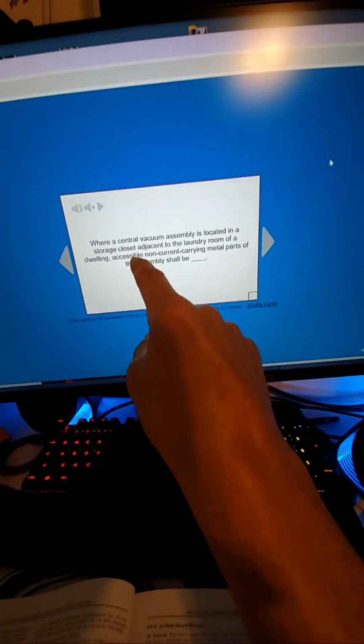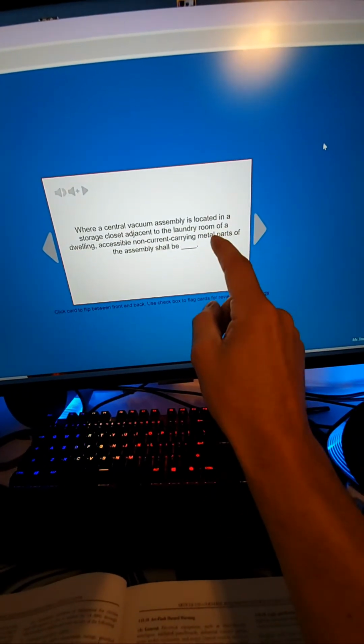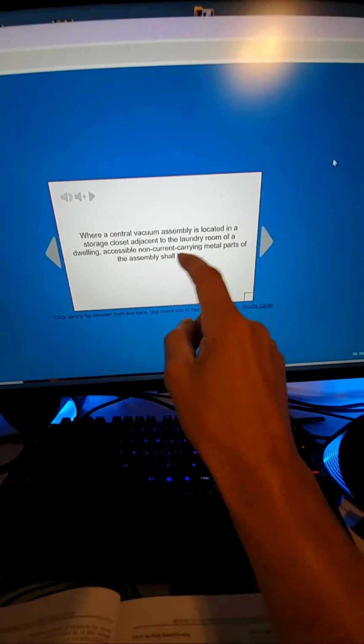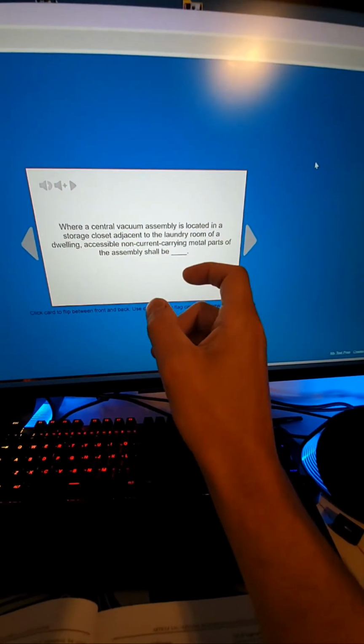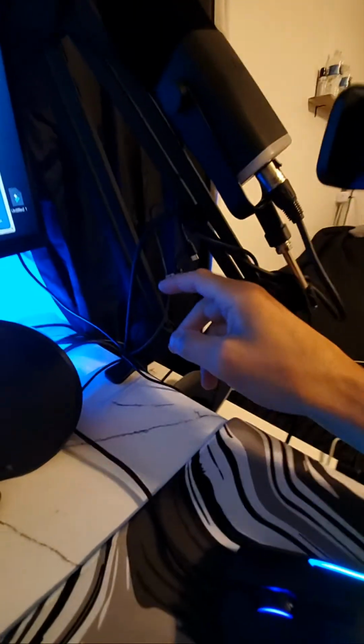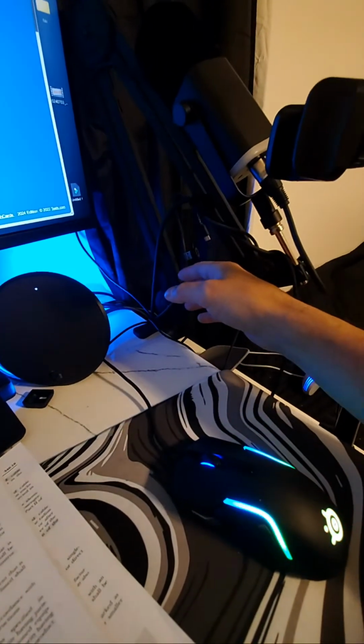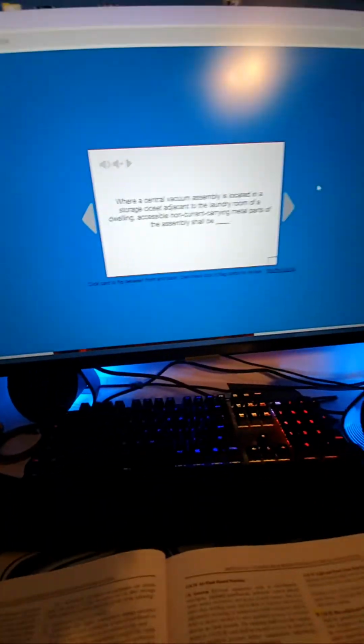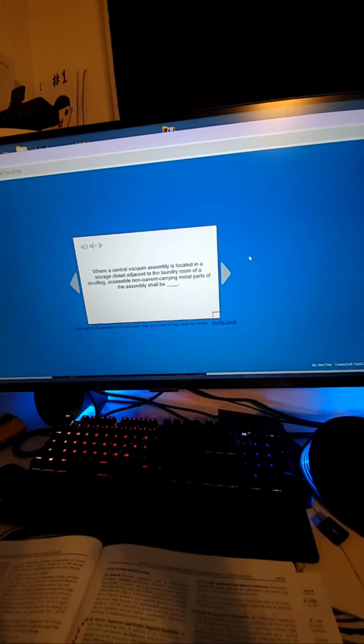So in this case, they want the non-current carrying metal parts that can carry current. Just because they're non-current carrying means that they're not normally current carrying. So you could say that this mic stand is non-current carrying because typically there's not supposed to be any current on here. But if this was permanently installed and it was part of something that had voltage attached to it in some way, whether it had a receptacle attached to it or something, you would need to bond the case of this mic stand to the source. So the answer is going to be bonded. Let's see if we can find it.